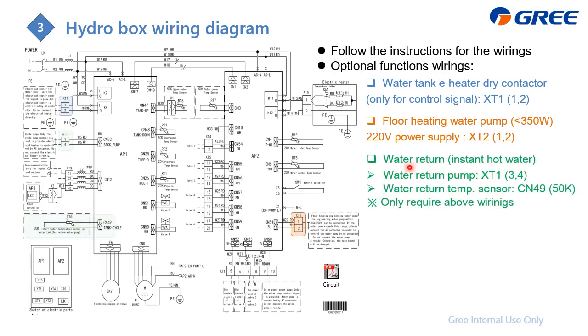Next is the water return, which is the instant hot water. At that time, we need to detect the water temperature, which is from the CN49. It is a 50 k ohm water temperature sensor. If we detect the temperature is less than the preset value, and also during the preset time, we can turn on the water return pump, which is this one, to circulate the water. And later, I will explain how the system operates.